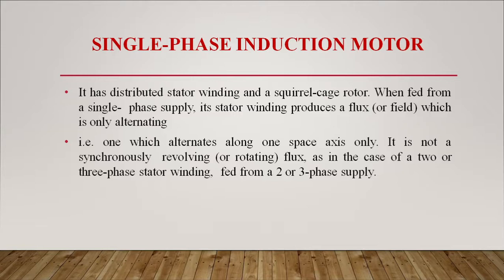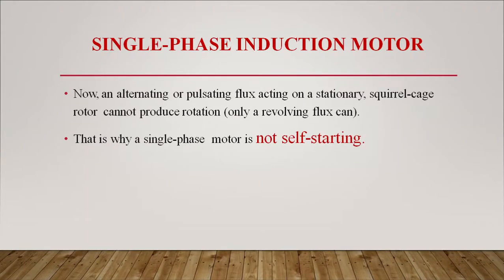The stator winding of a single phase induction motor produces only an alternating flux, not a rotating magnetic field as in a three phase induction motor. An alternating or pulsating flux acting on a stationary squirrel cage rotor cannot produce rotation — only a revolving flux can produce rotation. That is why the single phase induction motor is not self-starting: there is no rotating magnetic field (RMF) and hence the rotor cannot rotate.